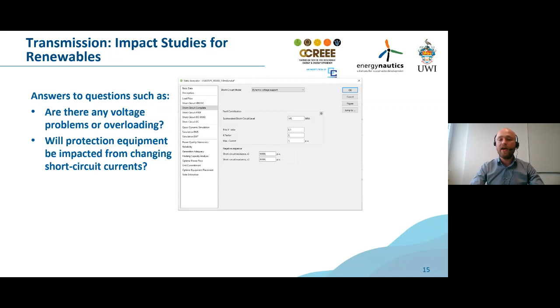and also whether dynamic stability will be maintained. You need specific dynamic models for your RMS and EMT simulations, and you really have to take care that these are accurate. As Sanji mentioned before, steady state analysis is something you can achieve relatively easily in any power system analysis model, and set up your model for that.